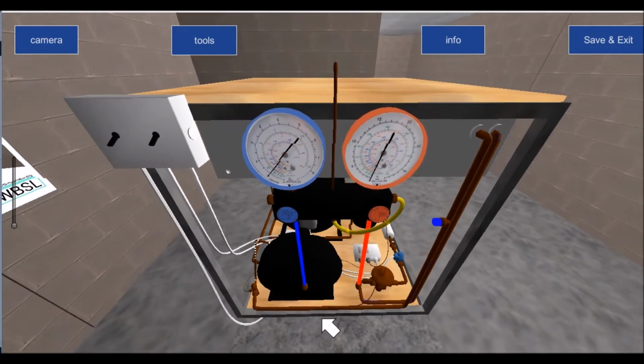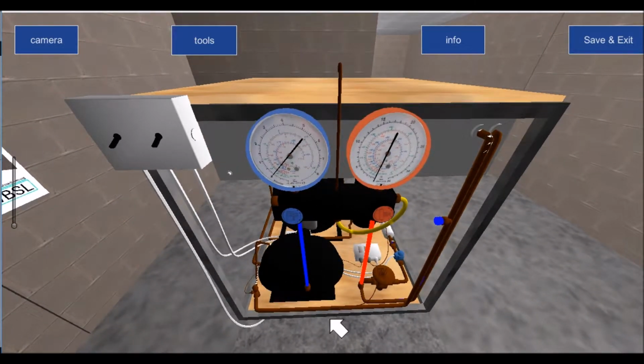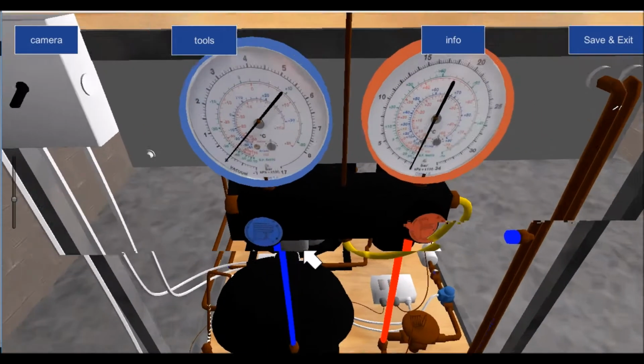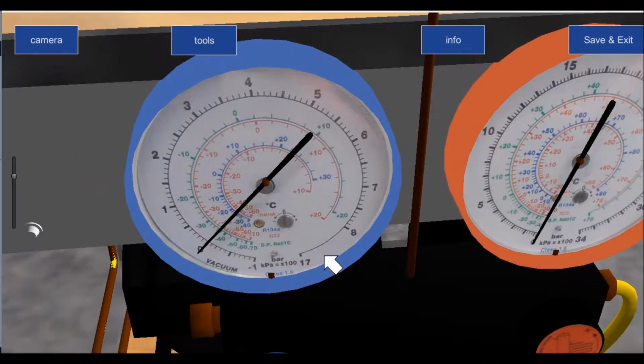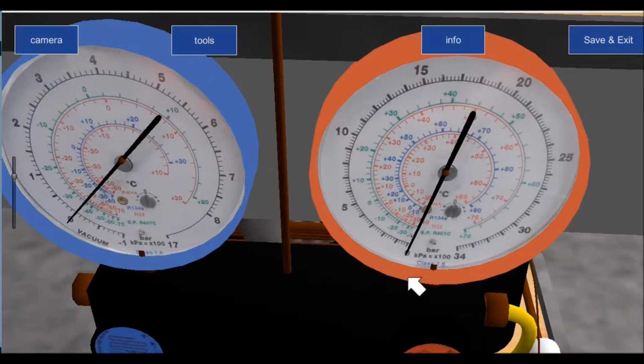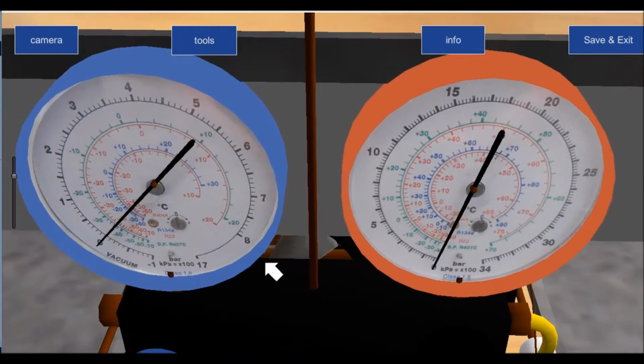Now, what I keep saying to you is that we have to concern ourselves about high pressure, high temperature vapor and high pressure, high temperature liquid. And then I talk about subcooled liquid and I talk about superheat vapor. So what we need to remember is that refrigerant gases work on the principle of pressure-temperature relationship. So they have a pressure-temperature relationship. So when we look at our service manifold, okay, this is our service manifold, and we can see on the low side we go up to a pressure of 17 bar here, and if we look over on the high side we can see that we go up to a pressure of 34 bar. So that's how you first of all differentiate the two gauges.